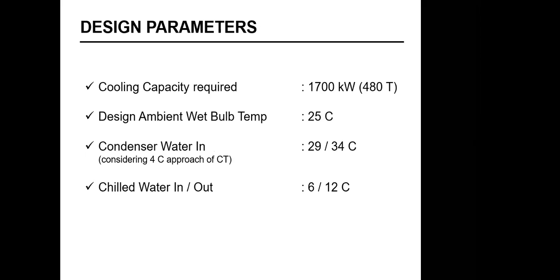So what happens? These are the typical design parameters given by a consultant. He says, I need a 1700 kilowatt cooling capacity chiller operating at 6 and 12 degrees centigrade chilled water conditions, and my design ambient is 25 degrees C. So I need condenser water in and out at 29 and 34 degrees centigrade. This is the parameter given to me as a chiller supplier. Similar parameters are given to a cooling tower manufacturer, because he has to select his tower based on this. Then all of us select our equipment and submit it to the customer. So here is a pitfall.